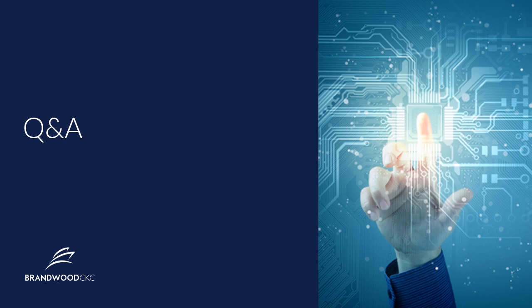Now, it will always come back to your documentation and your risk analysis as to how that process was accomplished and whether it was significant enough to mitigate the risk. And that will be up for your notified body to determine. But in general, that's a good place to start. I would definitely recommend the use of that standard as you think about clinical studies or studies on IVDs using human analyte samples.